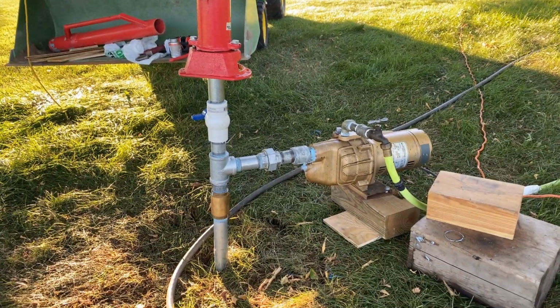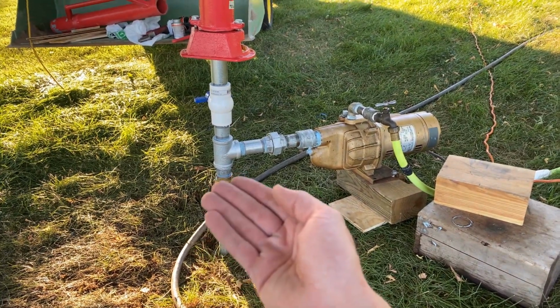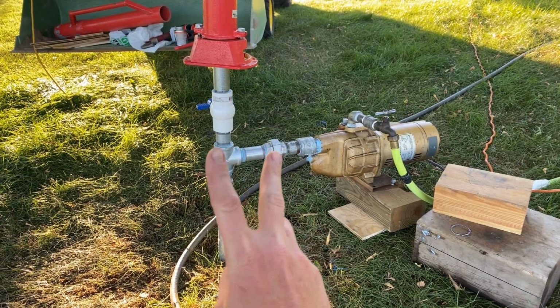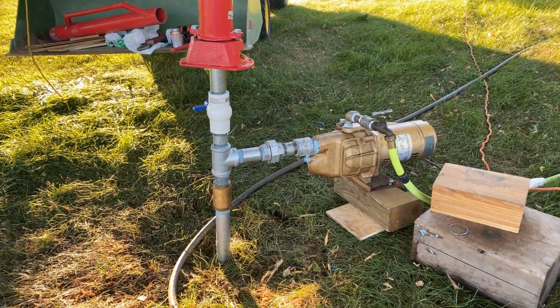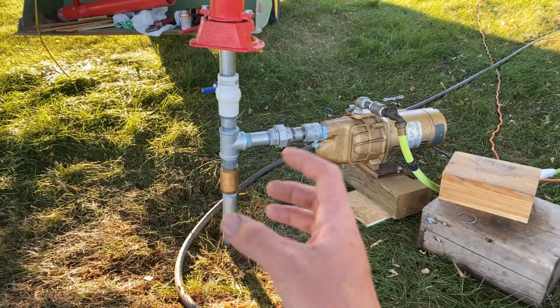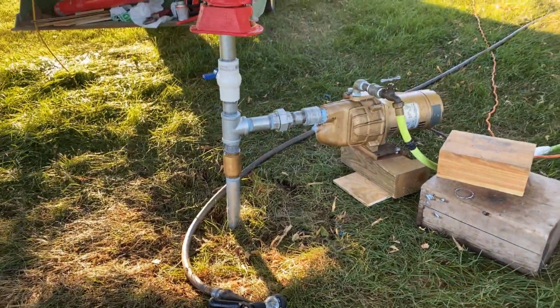Have you ever heard of positive air pressure coming up enough that it's actually bubbling up through the check valve? I've had two check valves, and it's enough that it pushes up. Have you seen that? Again, positive pressure, not just like a leaky coupler. Or is it a leaky coupler? I mean, we're down a long ways. Where would that air be coming from?